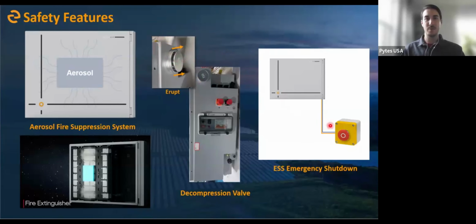And then lastly, we can now do ESS emergency shutdown. There is a physical circuit breaker on the V10 battery. I'll hit on that a bit more later, but you can connect a manual push button, an emergency stop button, something like you see here, to our battery, and pressing the button will send a signal to the battery, which will then cause the battery to trip the circuit breaker. So this is something that we can't do with our V5 currently, but the catch here is that the V10 has a circuit breaker built in while the V5 doesn't.